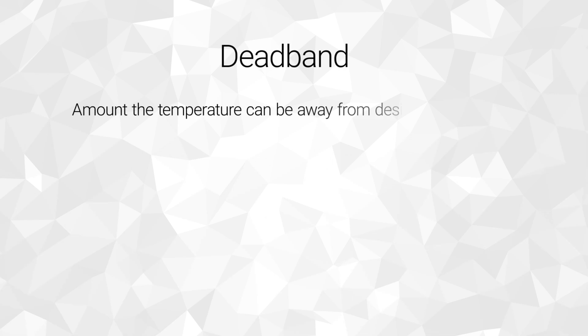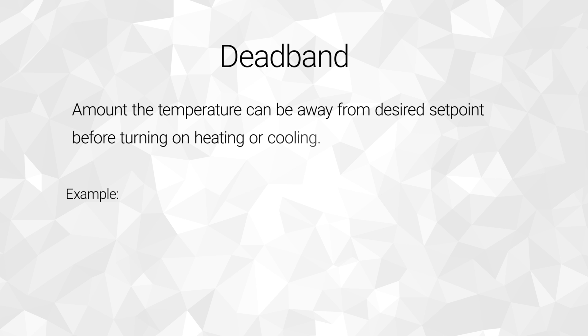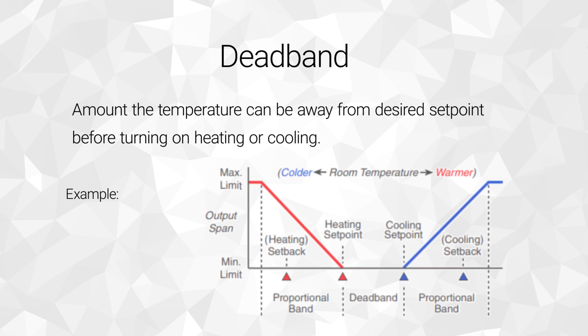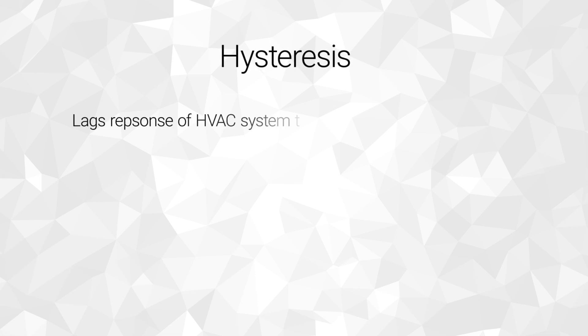Dead band is the amount the room temperature can move away from the desired set point before turning your heating or cooling system on. For example, if we set a thermostat to 74 degrees in the winter and it has been configured for a dead band of 4 degrees, heating will not be triggered until the room reaches 70 degrees. This ensures that the system is not constantly turning on or switching between heating and cooling with every minor deviation from the set point.